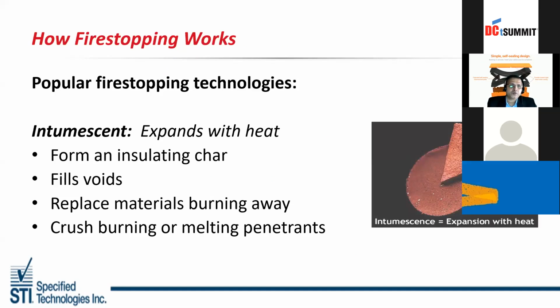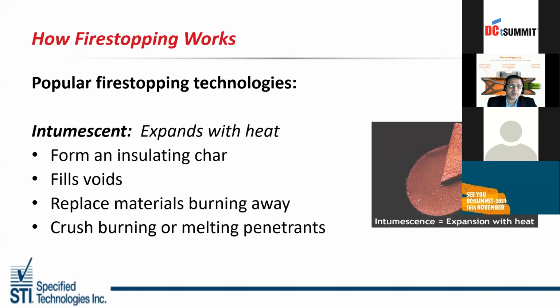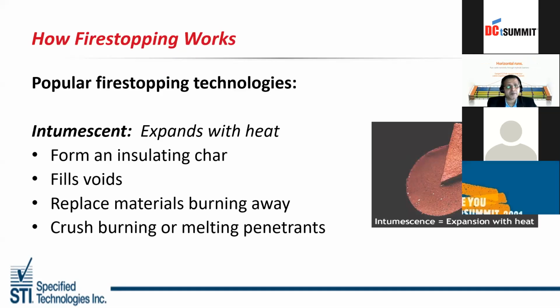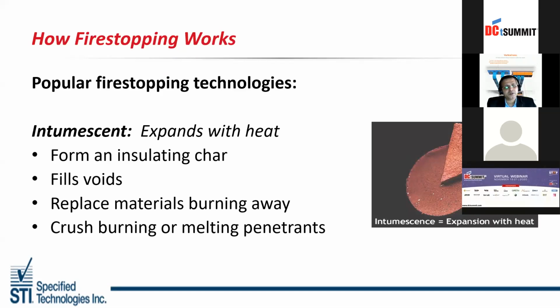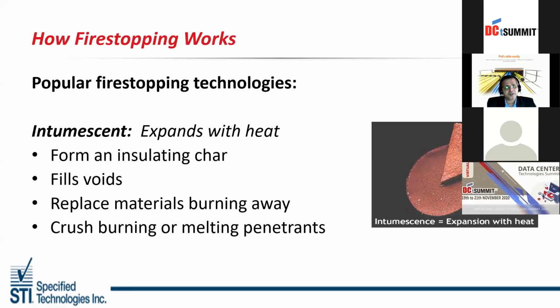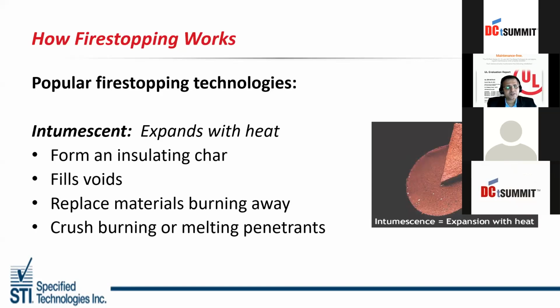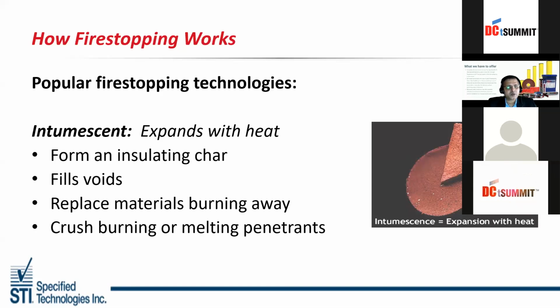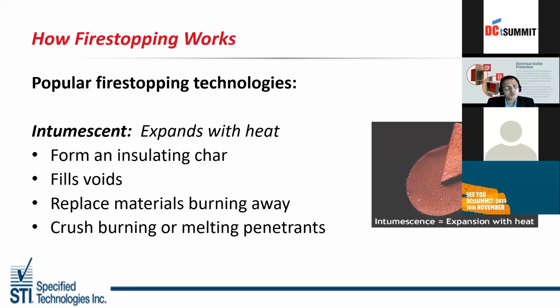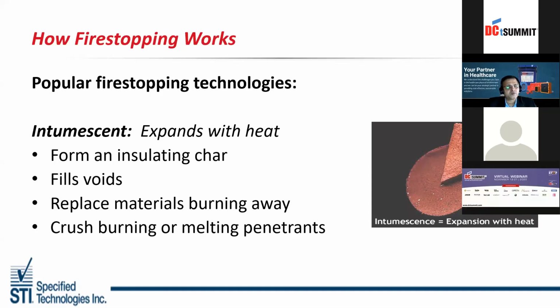How fire stopping works: the most popular products for combustible cables and combustible pipes are intumescent products. Intumescent products are those which expand in case of heat. It should be around 170 to 180 degrees. Once it reaches that temperature, the sealant starts expanding. Once it starts expanding, it will crush the pipe or the cable, and it will stop the passage of fire and smoke to the upper floors.